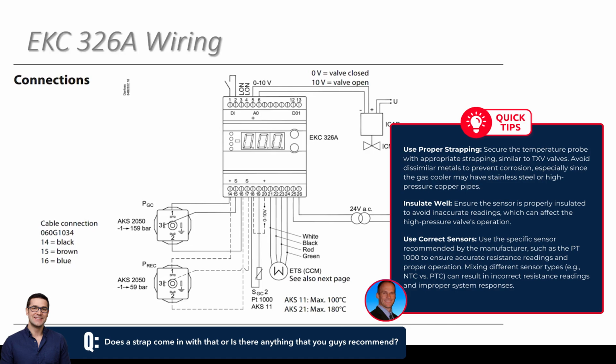Is that the same with the PT1000 that you guys sell? We always would want to see this one. We know that there aren't issues with it. We've seen, not just maybe in this application, but even on the case side where it's the same type of sensor, PT1000, that third-party sensors have been used, and whether it's tolerance or the temperature to resistance ratio isn't the same, we've seen issues with that. Yeah, so just make sure, it doesn't matter, always get the one that the manufacturer of that specific controller recommends. It'll save you a lot of grief.